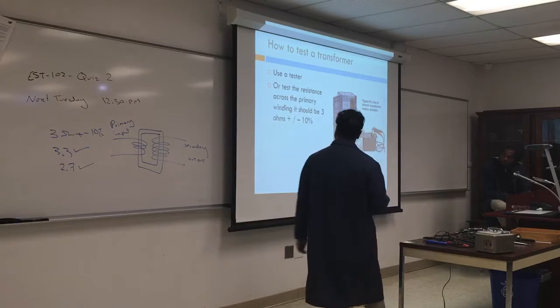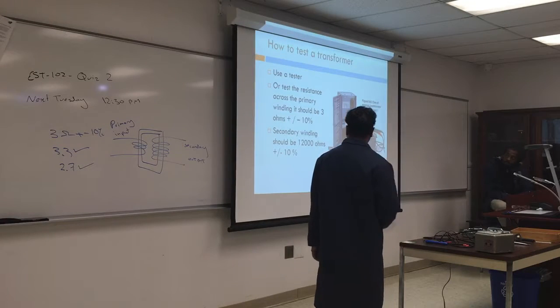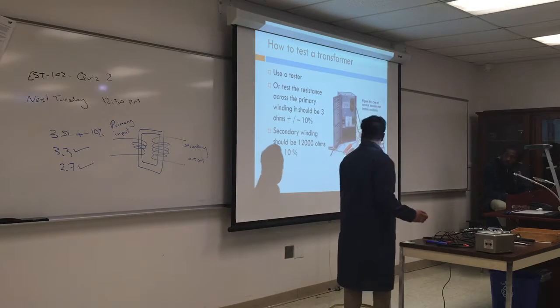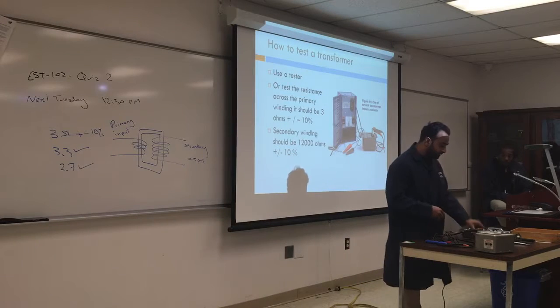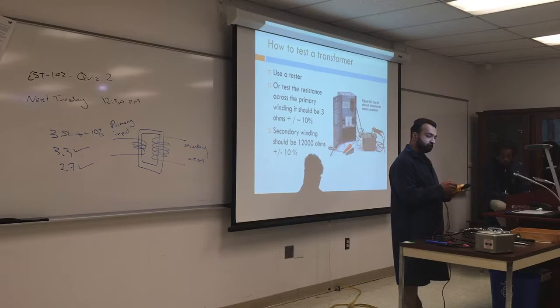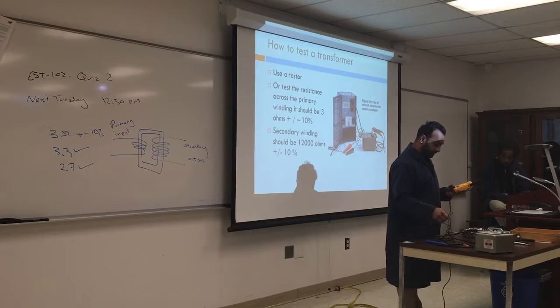So this one will test it. Secondary winding should be around 1200 ohms plus or minus 10% as well. What's gonna be the problem if it's higher than that? It's gonna give you more of a problem if it's higher. It's not doing the right transformation. Yeah, the transformer's not good at that point.